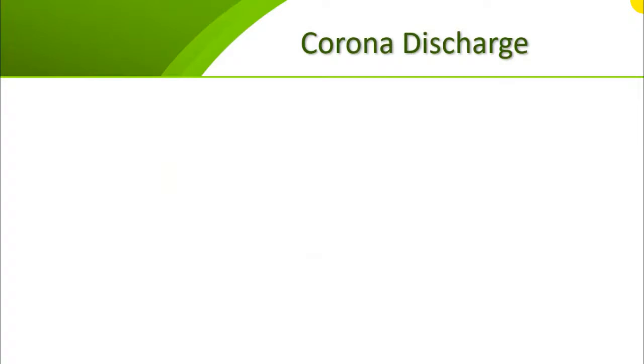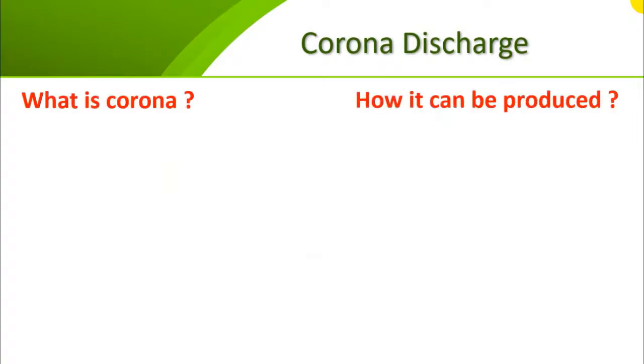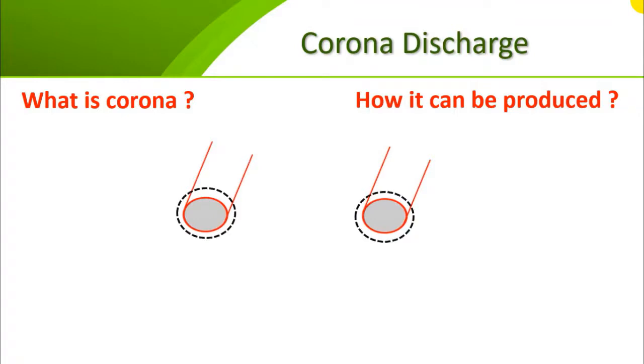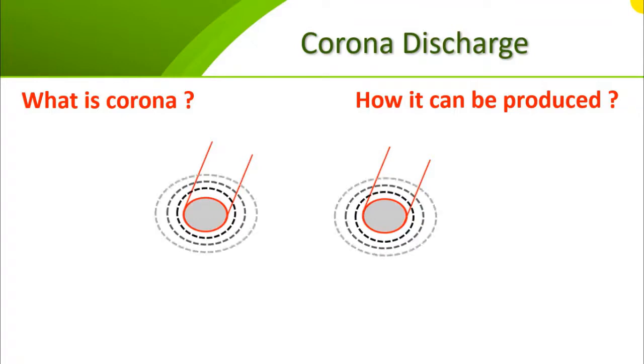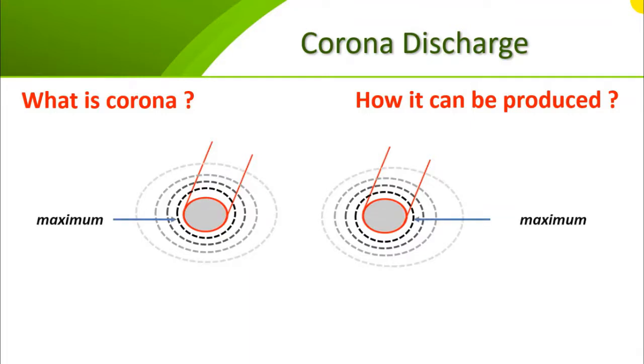First of all, let's see what corona effect is and how it's produced. To understand how corona discharge is produced, let's say that we have two conductors in parallel, separated from each other in air. These two conductors carry electricity at high voltage. Since the two conductors carry electricity and voltage, each conductor will produce its own electric field as shown. The electric field intensity will be maximum at the surface of the conductor, and the electric field decreases as we move away from the surface of the conductor.